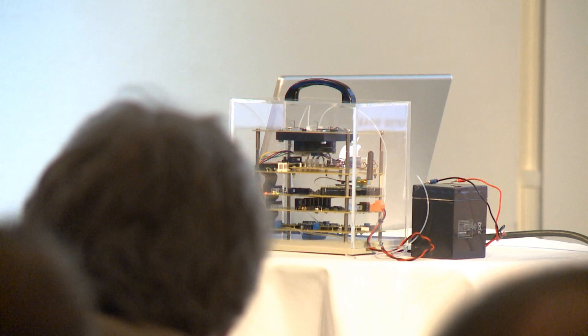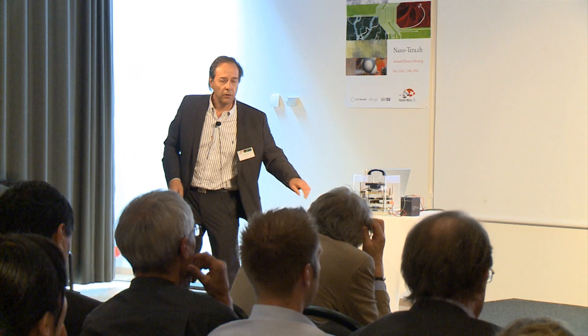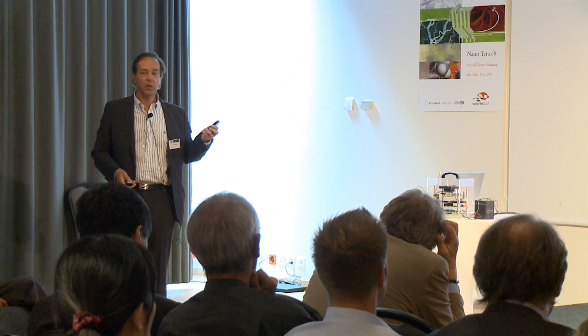At the University of Applied Science in Sion, in the group of Marcel Geyser, they developed a compact fluorescence module combined with microfluidics. This is what you have on the table here. For the moment it's rather big, and we make it with stacks because it's easy to exchange and optimize. There is one microfluidic layer, a layer for the fluorescent sensor, a layer for data processing, a power supply, and a micropump for perfusion. What you have on the table is the demonstrator.